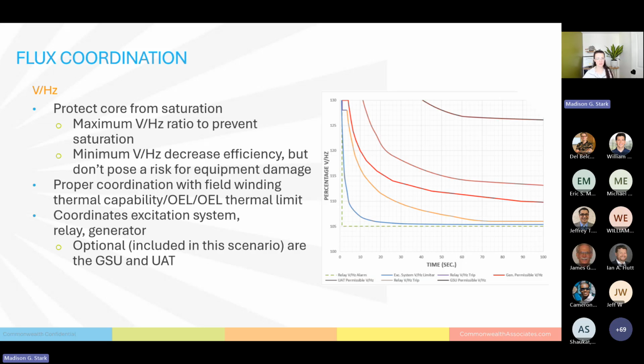So what we see on this volt-hertz graph, and you'll notice it looks very similar to a time current curve or an inverse time plot: you have your time on your horizontal axis, and then you have your percentage volt-hertz ratio on your vertical axis, sorry. And again, same thing, we're going to work all the way from this corner down here, and we're going to bump our way out to make sure that our elements are coordinated. So we want to hit that limiter first. Perfect. That's what we hit. Well, actually, we hit this alarm. Great. Not everyone has an alarm, not required. But we hit this limiter, which is what we want to see. And then we hit our relay trip. Perfect. And then we hit the generator limitation for that volt-hertz ratio.